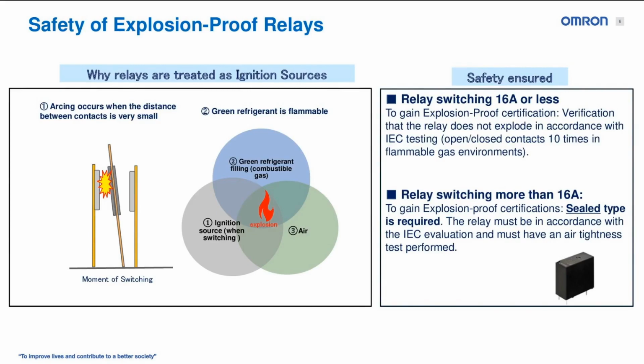And to ensure that safety, we look at relays in two categories: relays switching 16 amps or less and relays switching more than 16 amps. When we're talking about 16 amps or less, to gain that explosion-proof certification, we need to verify that the relay does not explode in accordance with IEC testing. That's typically opening and closing the contacts 10 times in a flammable gas environment. And when we're talking about switching 16 amps or less, this means that we don't need a sealed relay. It can be a relay that allows some gas within the internal components, as long as they do not ignite.